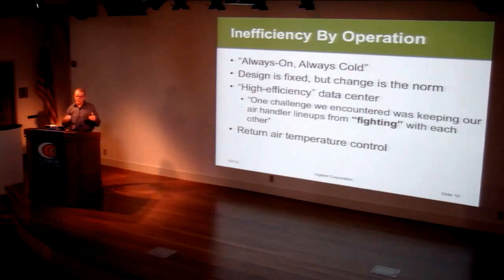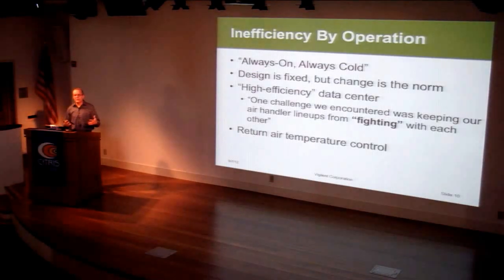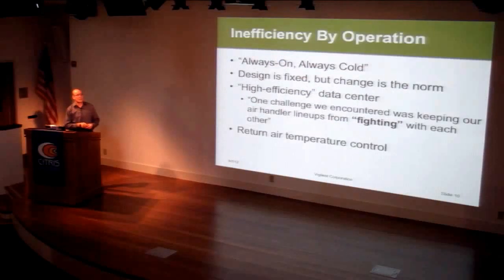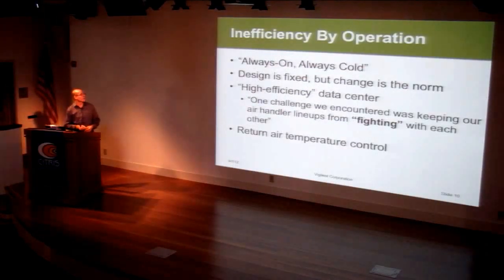This works two ways. If you keep a data center very cold, you're transferring heat into the floor, walls, ceiling, and everything outside the data center. In a lightly loaded data center, that loss is a bigger fraction than in a heavily loaded one, where so much heat is generated inside that the parasitic loss to the outside is negligible. But by raising the temperature of the data center, you can improve the efficiency of the air conditioning equipment—so an always-cold strategy really destroys the efficiency of the equipment.